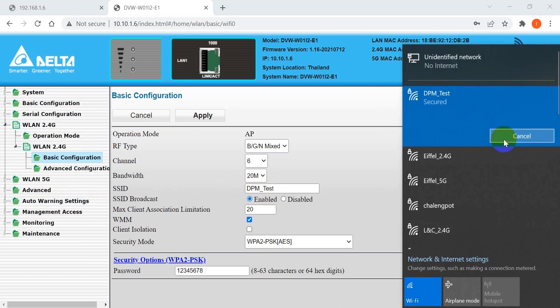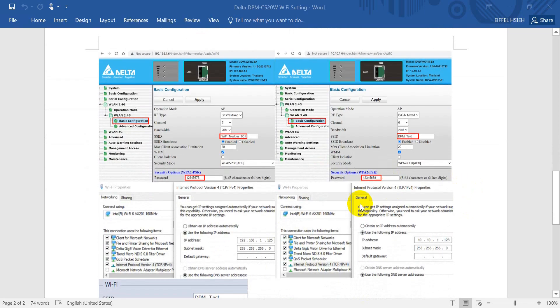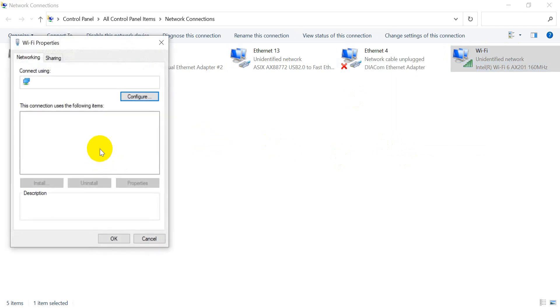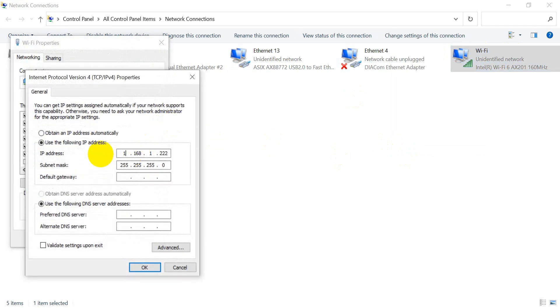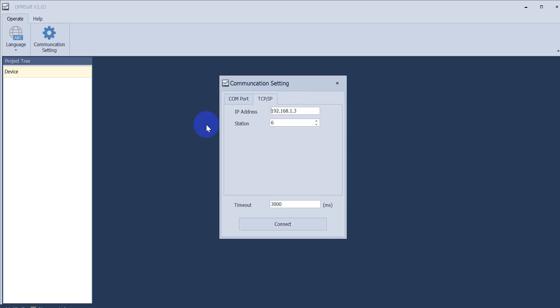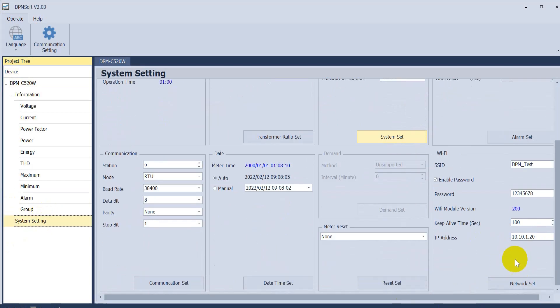You will see DPM_test listed. After we connect to the access point, remember to modify your laptop IP again. Then go back to the DPM software. The IP address assigned is 10.10.1.20 and station ID remains 6. Click connect, and we can go back to check — everything works fine.